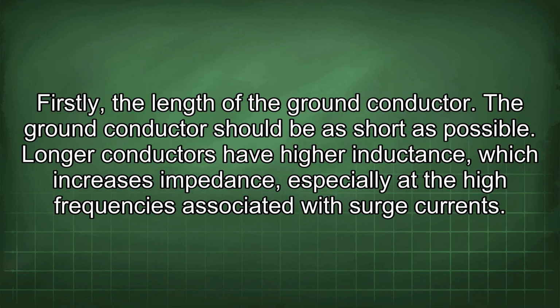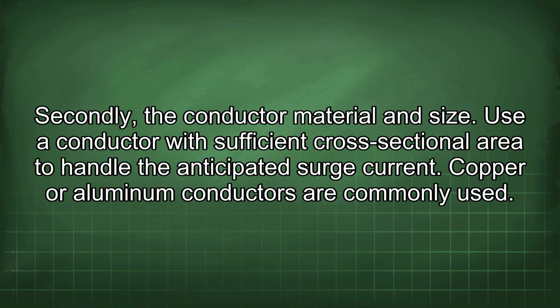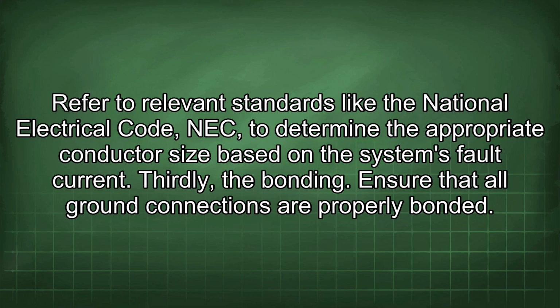Firstly, the length of the ground conductor. The ground conductor should be as short as possible. Longer conductors have higher inductance, which increases impedance, especially at the high frequencies associated with surge currents. Secondly, the conductor material and size. Use a conductor with sufficient cross-sectional area to handle the anticipated surge current. Copper or aluminum conductors are commonly used. Refer to relevant standards like the National Electrical Code, NEC, to determine the appropriate conductor size based on the system's fault current. Thirdly, the bonding.